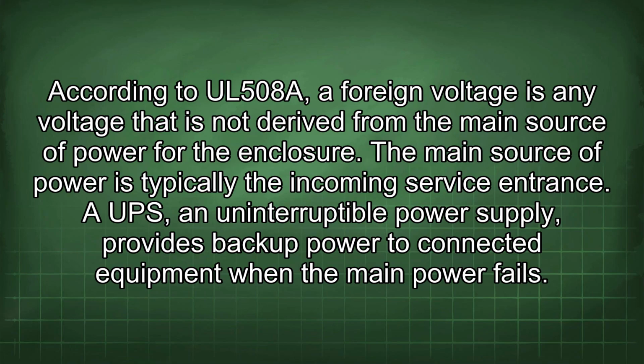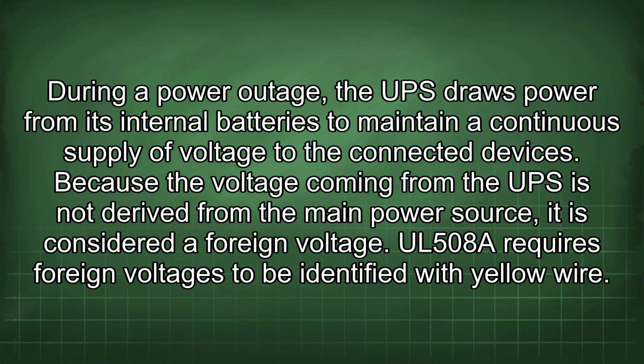According to UL508A, a foreign voltage is any voltage that is not derived from the main source of power for the enclosure. The main source of power is typically the incoming service entrance. A UPS, an uninterruptible power supply, provides backup power to connected equipment when the main power fails. During a power outage, the UPS draws power from its internal batteries to maintain a continuous supply of voltage to the connected devices. Because the voltage coming from the UPS is not derived from the main power source, it is considered a foreign voltage.